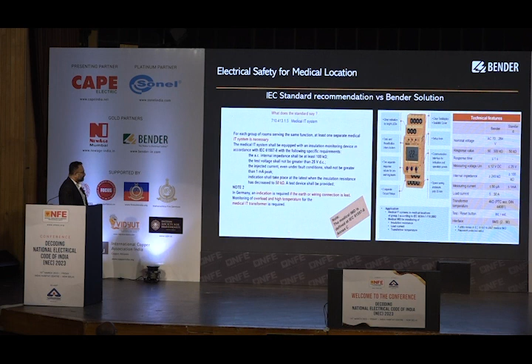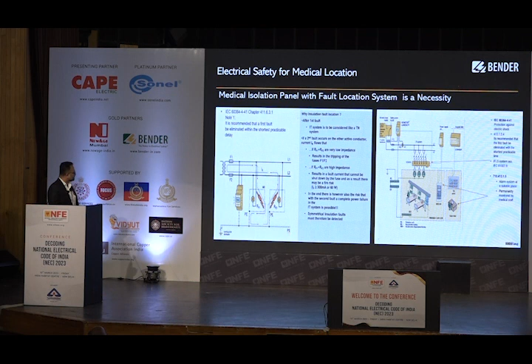So Bender also follows that standard, and we are manufacturing that type of insulation monitor for healthcare systems. We are putting that type of insulation monitor in OT and ICU systems. With that we have fault location also, because if an insulation fault happens anywhere, it is very difficult to find by trial and error which sector and which equipment is faulty. So there should be a fault location system. Without tripping or shutting down the system, you understand which equipment, which branch and which circuit has the problem. That's why a fault location system is a must.